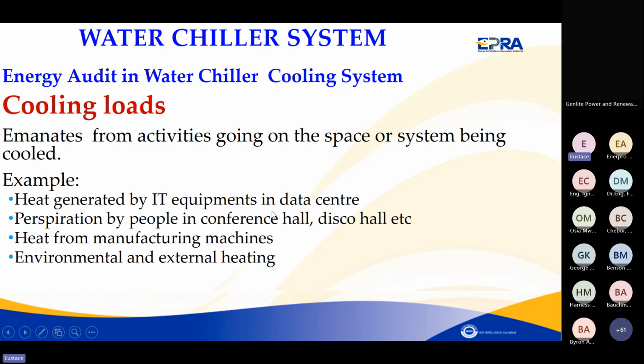Cooling loads in energy audits - where do you get the cooling load from? There's heat generated by IT equipment in a data center, and perspiration of people in a conference hall versus a disco hall. You can compare a conference hall and a disco hall to see where the cooling load is higher - I'd expect it to be higher in the disco hall, because people are jumping up and down, very energetic, releasing a lot of sweat, which requires latent heat of cooling.